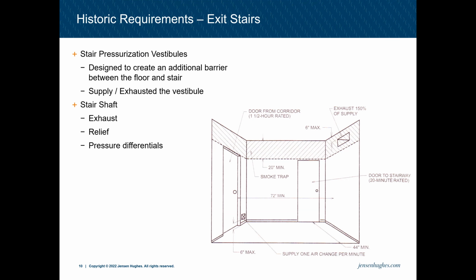These were no longer required for newer systems. The exhaust was designed at 150% of the supply, and the idea of this was that if smoke was coming close to our stair, we had a vestibule that could exhaust that additional smoke creeping in on our stair. Further research had shown that these vestibules don't add a large beneficial factor, so they have since been removed from the code. However, when we're working on older buildings that still have these systems in place, it is important that these systems are maintained to what they were designed to, so that they still function properly.